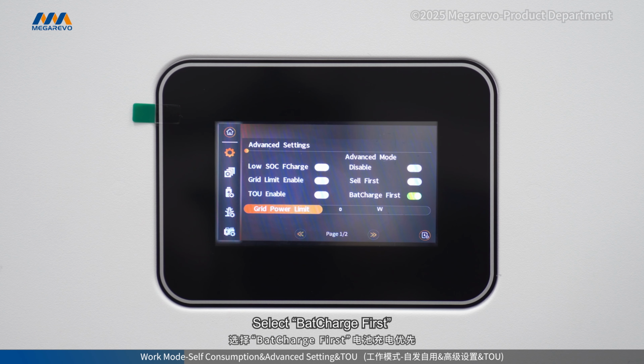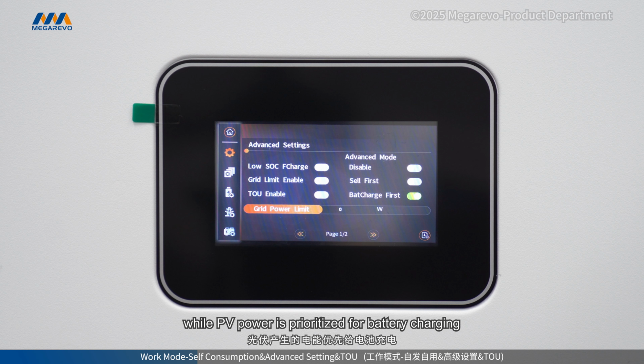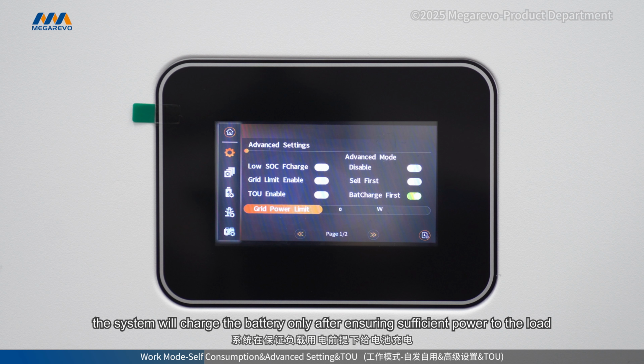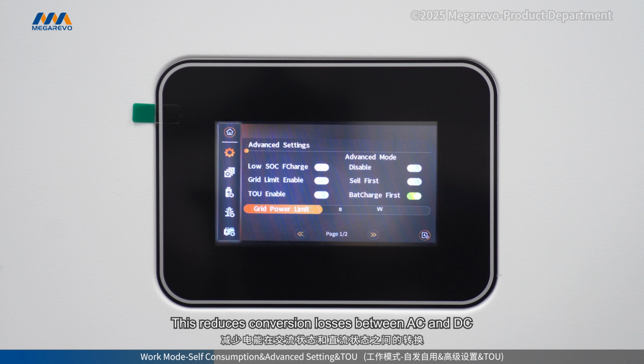Select BAT Charge first. In this mode, when the grid is available, the load is powered by the grid, while PV power is prioritized for battery charging. When the grid is unavailable, the system will charge the battery only after ensuring sufficient power to the load. This reduces conversion losses between AC and DC, and improves overall system efficiency.